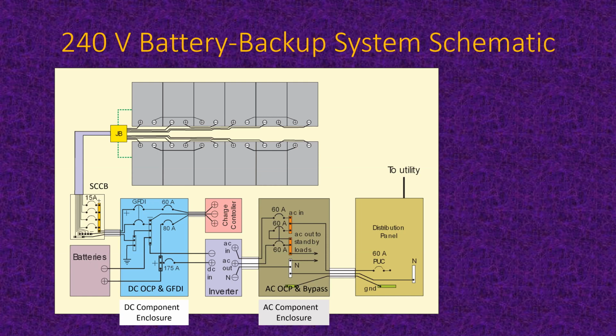So in other words, the charge controller is like a transformer in a way, except it's a DC to DC converter, and it converts a higher voltage into a lower voltage, but the power in equals the power out with maybe 1% loss at best. So therefore, you put in 60, you get out 80 at a lower voltage, just like a transformer transforming high voltage to low voltage. You go from low current to high current. All of it goes to that little positive bus bar, goes to the batteries, goes to the inverter, whichever one wants it the most gets it. And the charge controller is responsible for making sure that voltage doesn't go too high, because that would mean the batteries are overcharging, and then they are not happy with that.